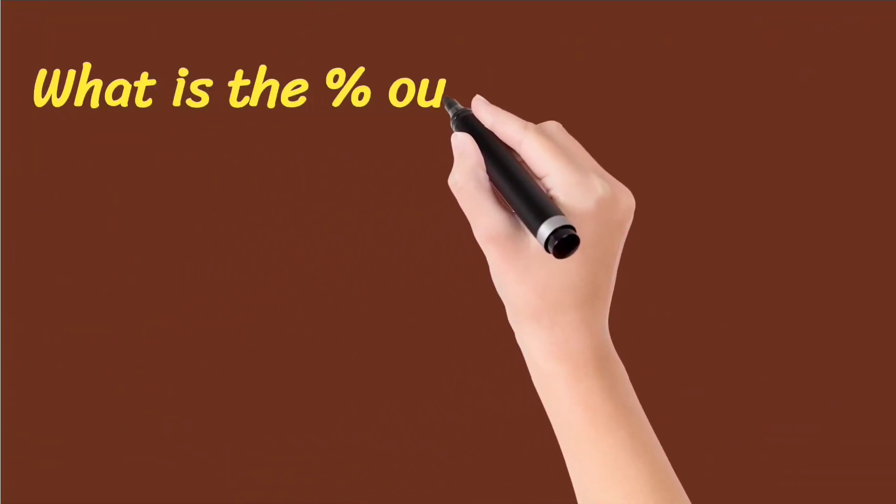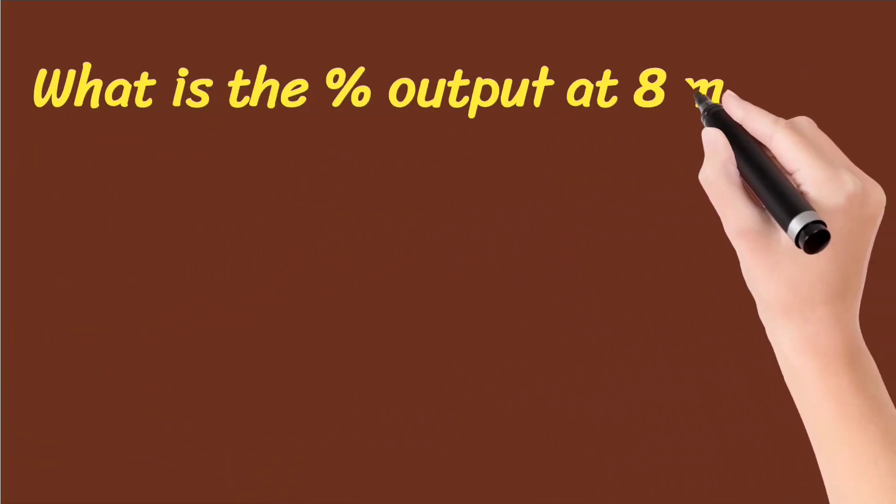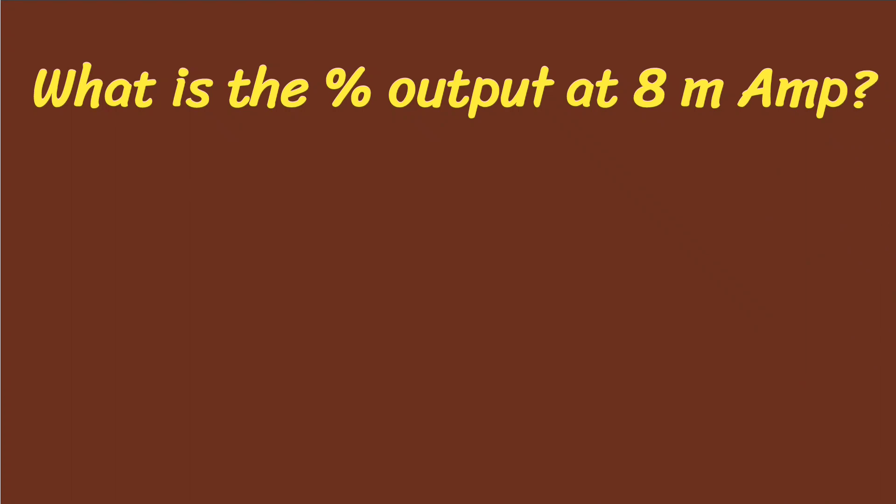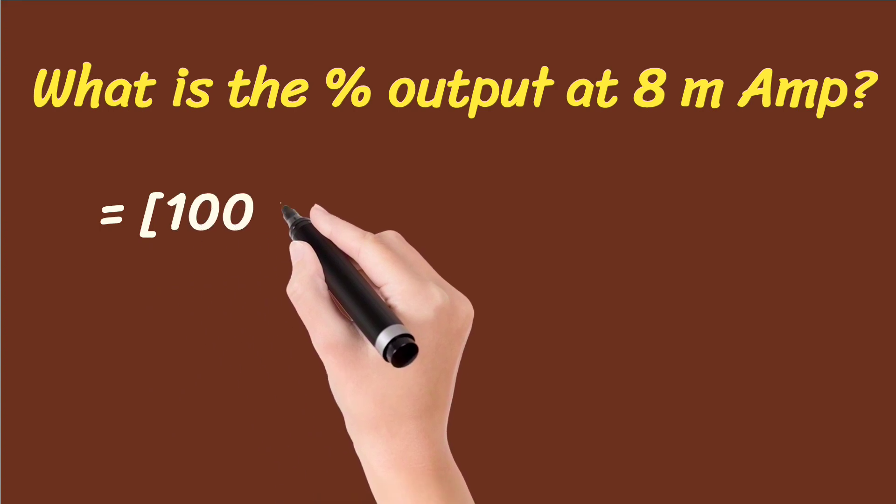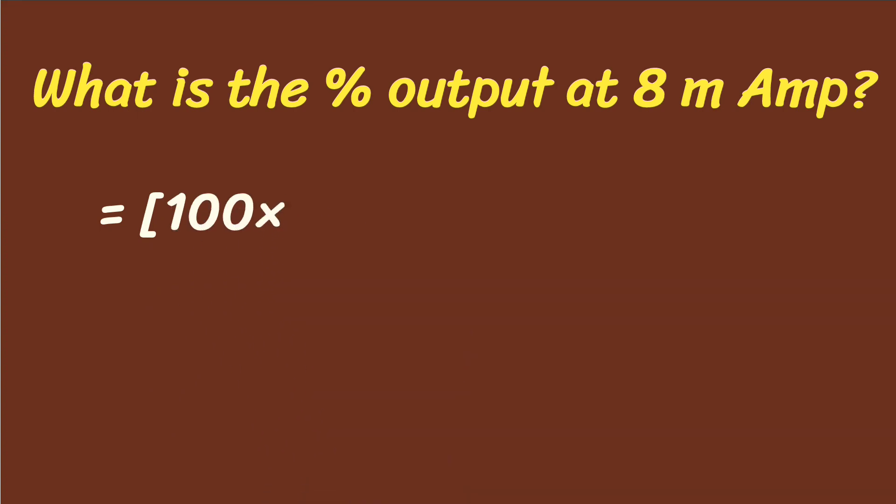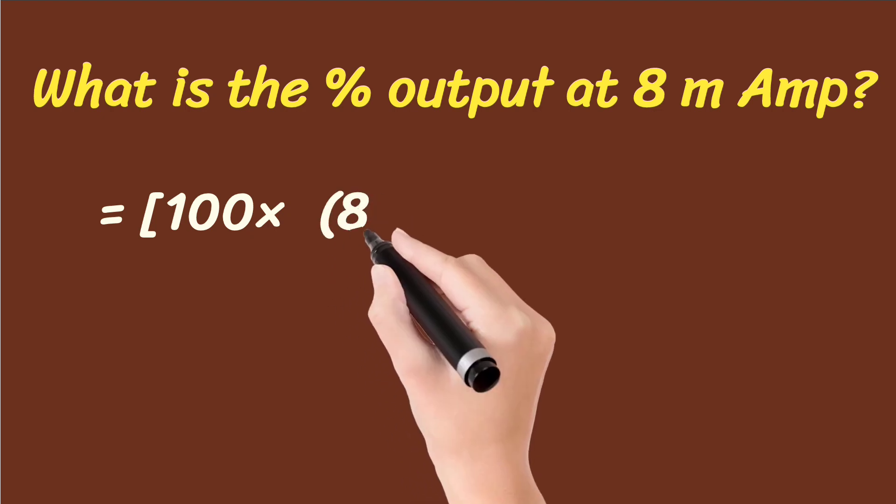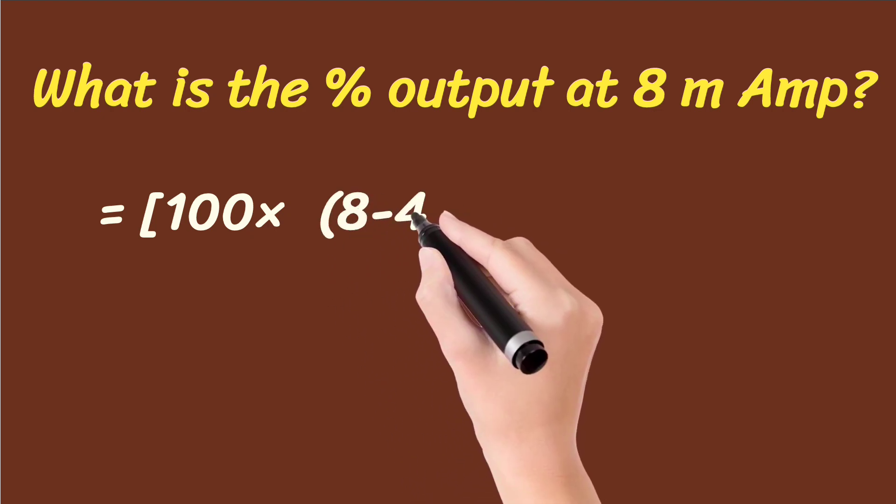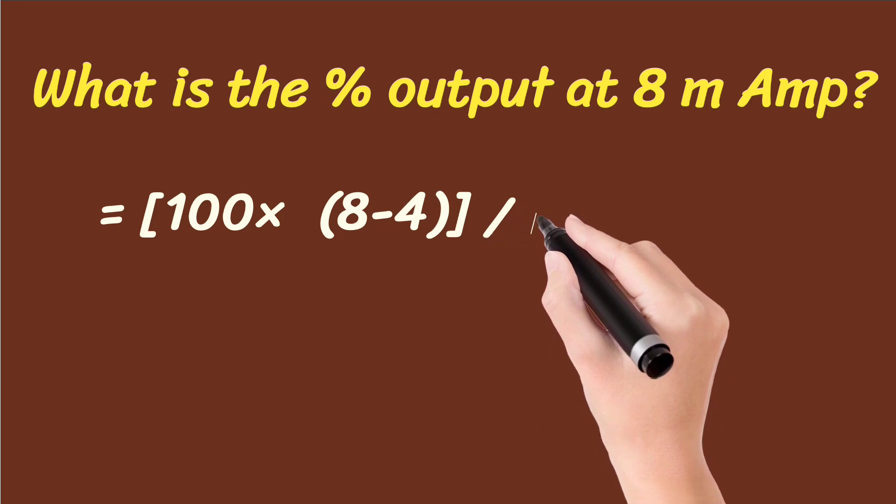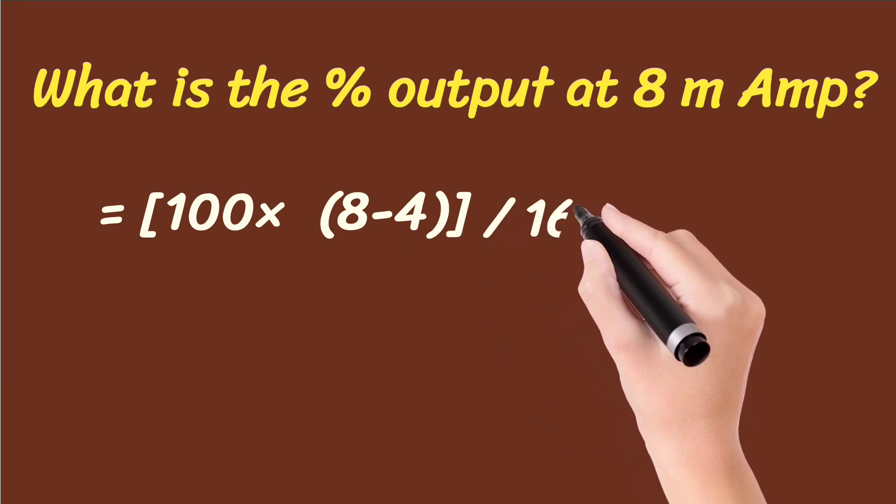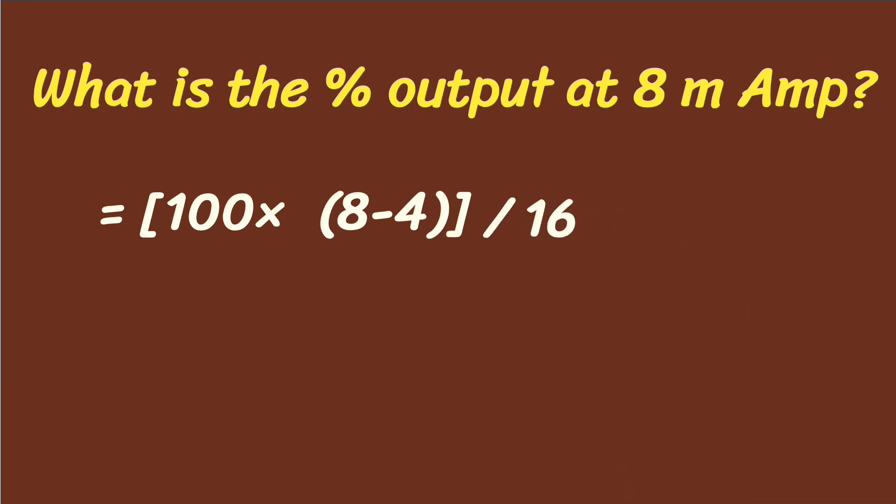Let's take the example of what percentage output will be at 8 milliamperes. So if you put the values in formula, then you will get 100, and milliamperes are 8, so multiplied by 8 minus 4, and divided by 16.